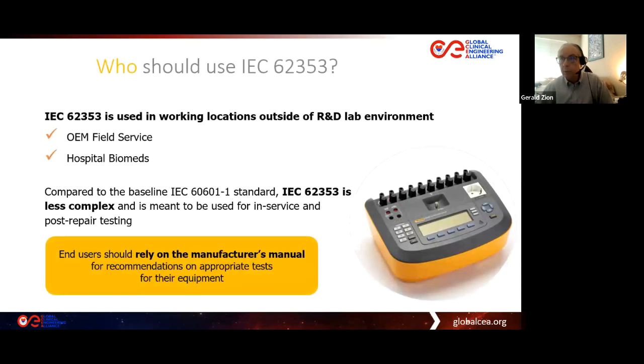All right, so who should use the other electrical safety standard under IEC 60601? And this is the IEC 62353. It's used in working locations outside the medical device manufacturer. So medical device field service engineers should be using this test method, this test standard, and we as hospital biomeds should be using it, even if we are using IEC 60601-1 for our acceptance testing or incoming inspection.